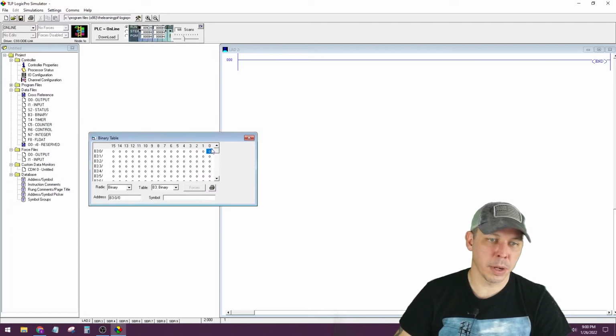They have to be tied to an output to change status. And they can be used the same as you would use if you think of a relay coil, you'd turn the relay coil on, so it would go from off to on, or 0 to a 1, and then there would be associated contacts with that relay that would switch states.